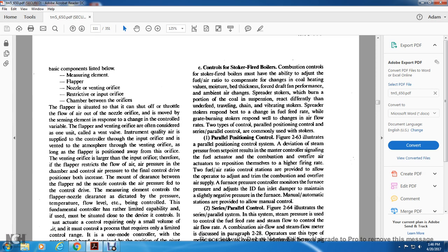One, parallel positioning control. Figure 2-63 illustrates the parallel position control system, with the deviation from the pressure set point resulting in the master control signal, signaling the fuel actuators and the combustion overfire air actuators to reposition themselves to the higher firing rate.